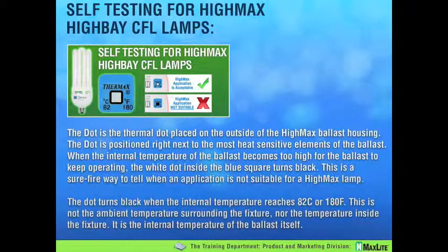One last important thing about HighMax technology and its applications: HighMax, like similar alternative light sources such as LED and induction, has heat issues. A bad or hot application is going to result in increased lumen depreciation — which can be very steep — and/or a very short lamp life. We don't like problems, you don't like problems, and most importantly, your customers don't like problems.